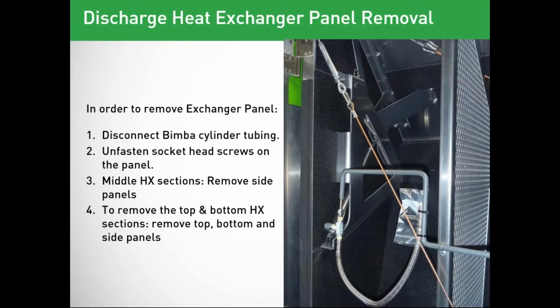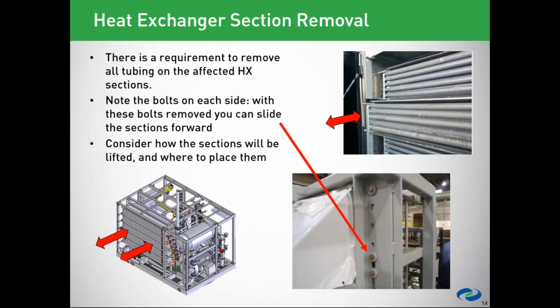In order to remove that heat exchanger panel, we're going to disconnect the bimba cylinder tubing from the louver doors, so the discharge louver doors. Then we're going to unfasten the socket head screws on the panels that surround this. These panels basically direct the airflow positively through the cooler sections. The middle heat exchanger sections, we remove only the side panels, and if we have to remove the top or lower sections of the heat exchanger, then basically all 4 panels around the opening have to be removed.